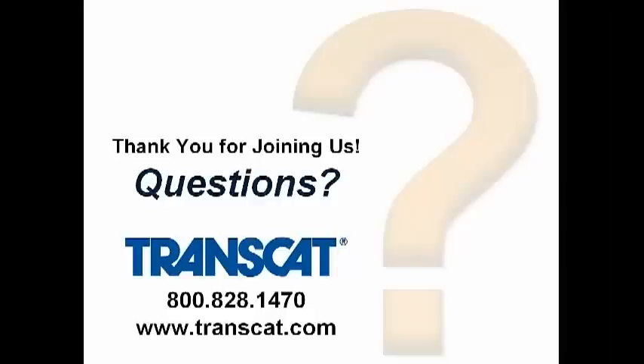Okay, we'll actually squeeze one more in before we wrap up. Is there a risk when using an OEM for calibration? Yes, there is. There can be. There are some OEMs who are very good at metrology as well as manufacturing products. There are some OEMs who have no idea what metrology is and what traceable measurement is, and it's obvious when you look at either their lack of a calibration procedure or the fact that they call an adjustment procedure a calibration procedure, and they start right out by adjusting the instrument without preserving as-found information.